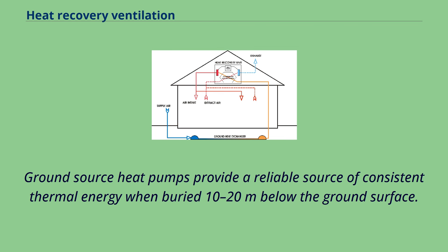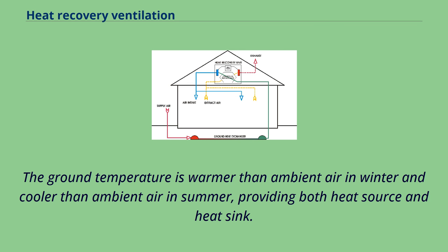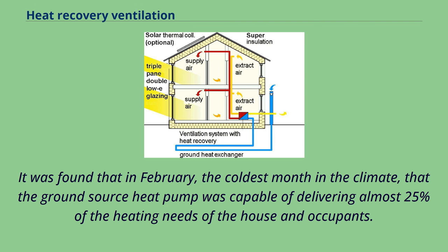Ground source heat pumps provide a reliable source of consistent thermal energy when buried 10 to 20 meters below the ground surface. The ground temperature is warmer than ambient air in winter and cooler than ambient air in summer, providing both a heat source and heat sink. It was found that in February, the coldest month in the climate, the ground source heat pump was capable of delivering almost 25% of the heating needs of the house and occupants.